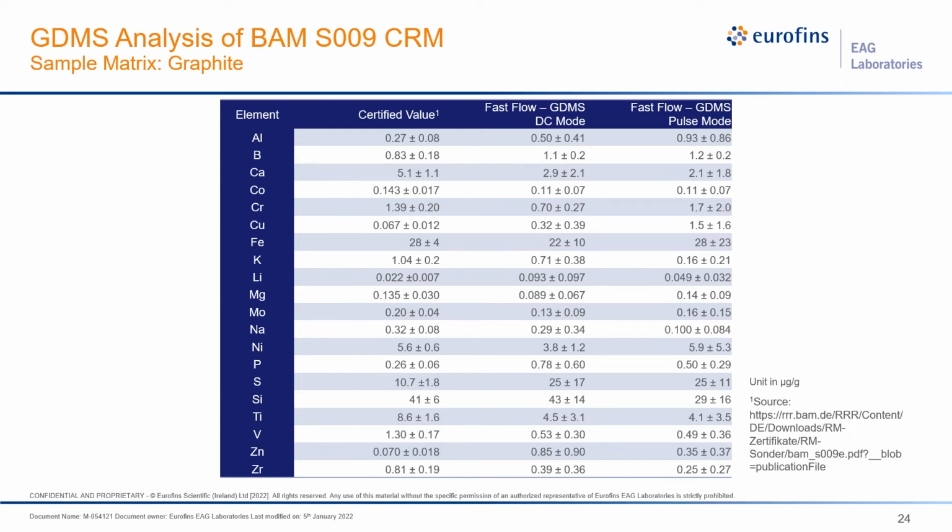One thing we want you to know is that for trace analysis, only when the impurity levels differ by an order of magnitude will we consider that statistically significant. Otherwise, you can see for solid samples, the impurity distribution is generally wider than in the solution mode.